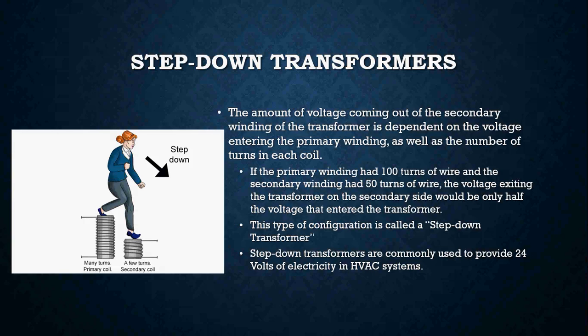A prime example of a step-down transformer in HVAC is a 120-volt primary to a 24-volt secondary. We use step-down transformers to provide 24 volts of electricity to power up our thermostats and to power up coils on relays, contactors, and things like that. A step-down transformer is really nothing more than a transformer that has more windings on the primary side and fewer windings on the secondary side.